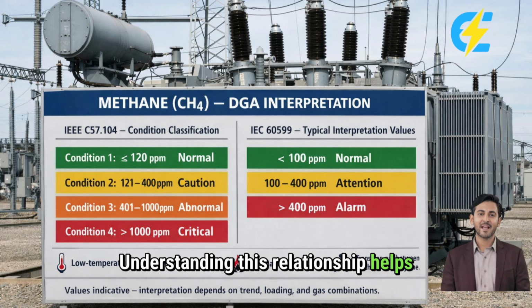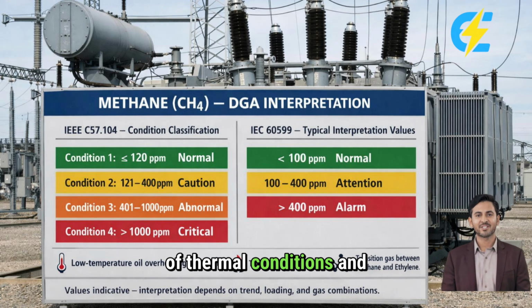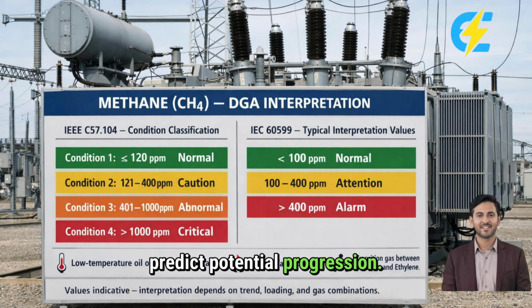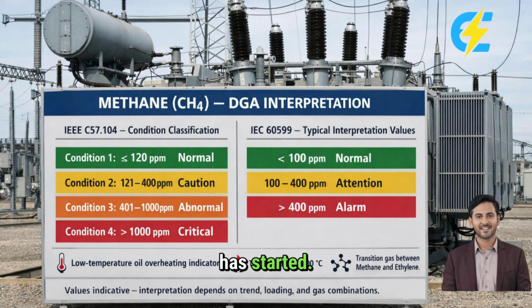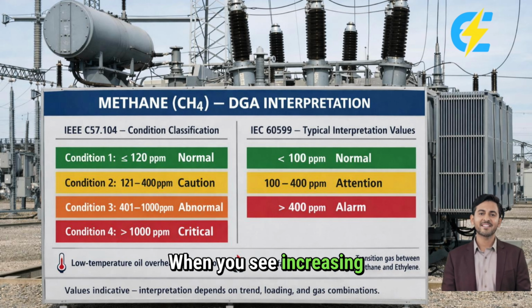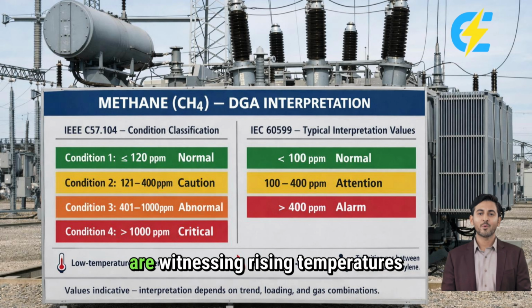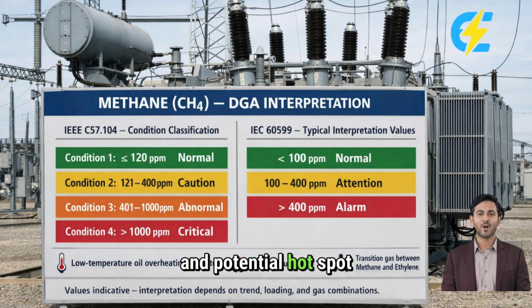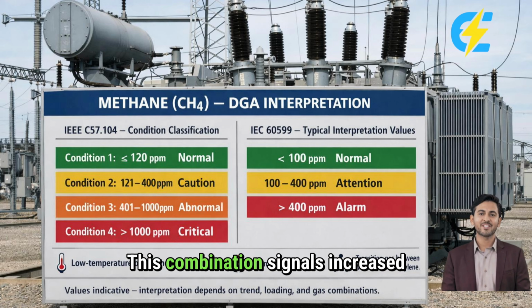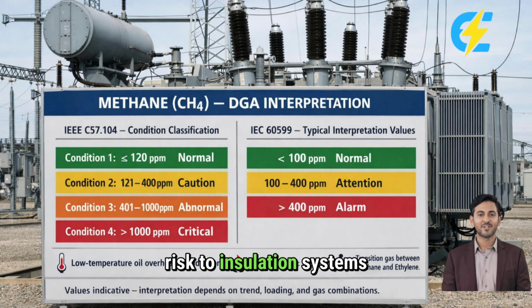Understanding this relationship helps you assess the severity of thermal conditions and predict potential progression. Methane tells you heat has started. Ethylene tells you heat is becoming serious. When you see increasing methane alongside ethylene, you are witnessing rising temperatures and potential hotspot development. This combination signals increased risk to insulation systems and requires prompt thermal analysis. The progression from methane to ethylene indicates escalating thermal stress that can damage oil and paper insulation if left unchecked.